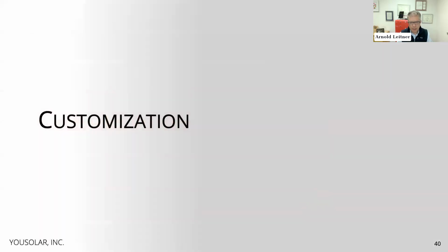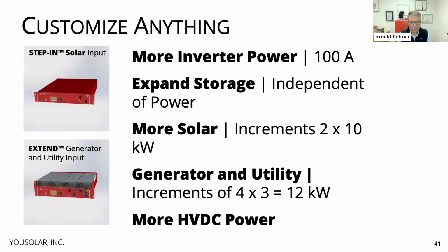Another thing that is unique about the PowerBloc, and I spoke about it at the beginning briefly, is its ability to customize. You saw the whole zoo, the whole collection of modules we have, and most importantly, the step-in and extend generator module are the most modules used to customize systems and bring in more solar. We have a home with 50 kilowatt of solar. That's not the limit. We have homes with 36 kilowatt of generator and utility integration. That's not the limit. But those modules then allow, when placed in the various cabinets, to customize the needs and expand the external energy inputs into the system.